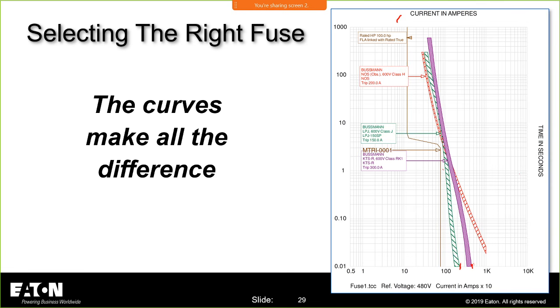Okay, so these are all fuses that can be used on that motor. And if you look in 430, they all fall within the proper limits. I think the full load amps on this is 120 some amps. If it's a dual element, I can go up to 175%. If it's not a dual element, I can go up to 300%.